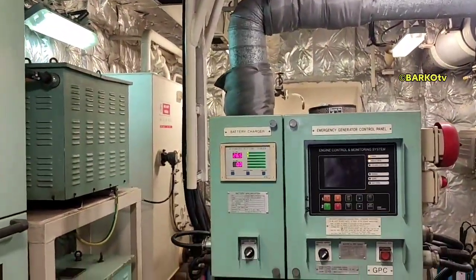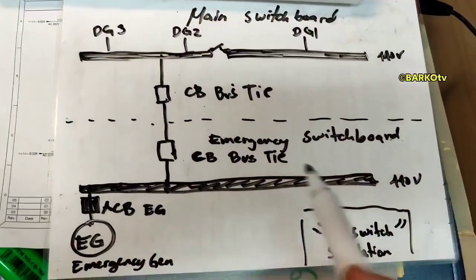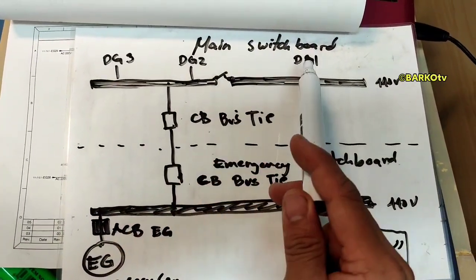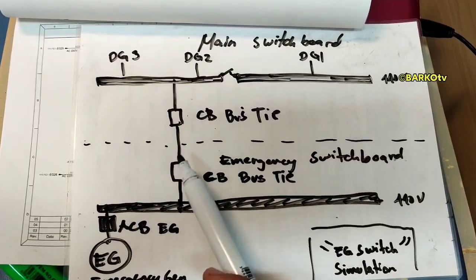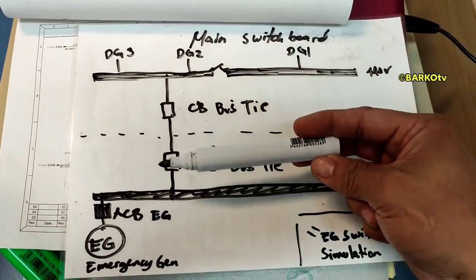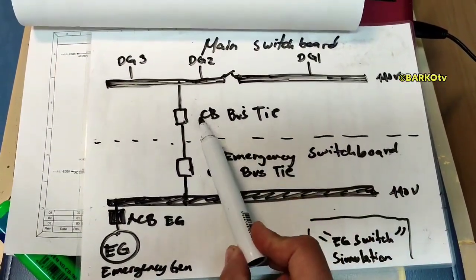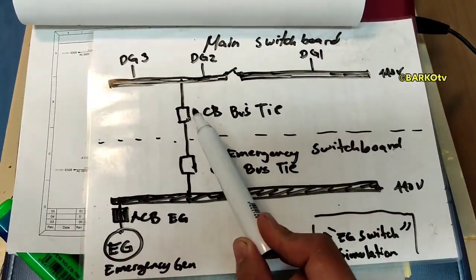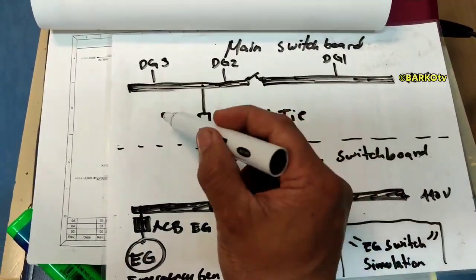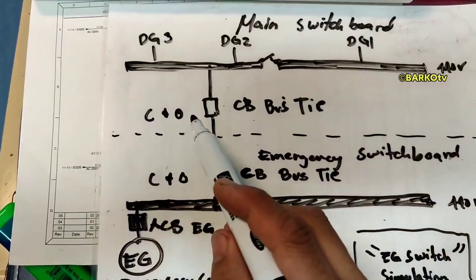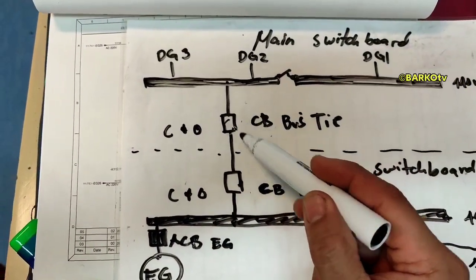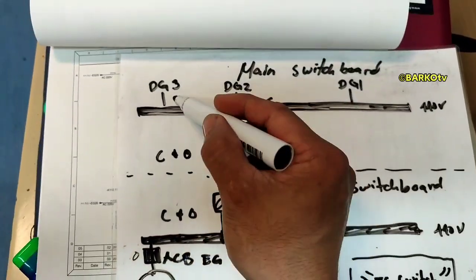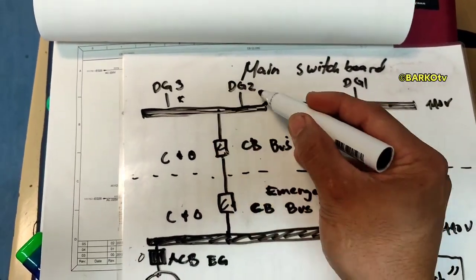This video is for emergency generator trouble during blackout test. For example, DG1, DG2, DG3 — there are two bus tie breakers. One is located at the main switchboard and one is located at the emergency switchboard. In normal operation this bus tie is close, meaning the main switchboard is supplying the emergency switchboard.